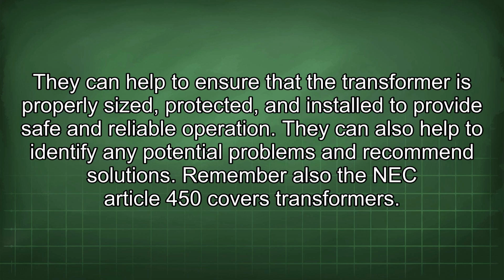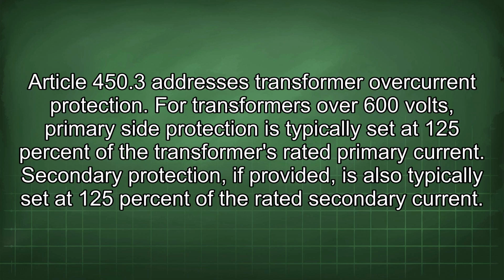Remember also that NEC Article 450 covers transformers. Article 450.3 addresses transformer overcurrent protection. For transformers over 600 volts, primary side protection is typically set at 125% of the transformer's rated primary current. Secondary protection, if provided, is also typically set at 125% of the rated secondary current.